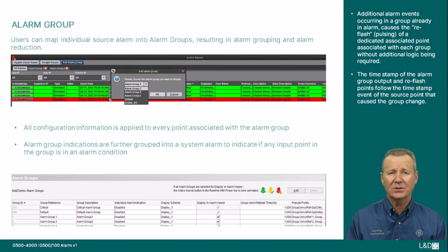The intent for these is to allow creation of alarms to be used only at the RTDB level for automation and reporting to SCADA. When the MCP HMI is used to display alarms, it is the end user's responsibility to ensure that operational alarms are always assigned to visible alarm groups.